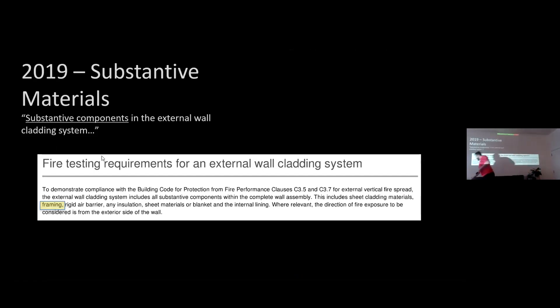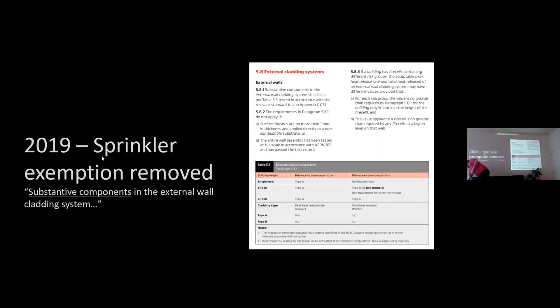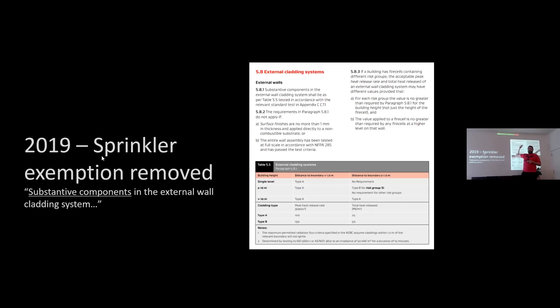2019 was actually a really important code clause for fires and combustible claddings — written really, really well. It had a couple of key things: it referred to 'substantive components,' which was a new concept — not just the cladding materials, not just the rigid air barriers. This was defined further on. It also said that now, even in sprinkler buildings, you can't just use whatever you want — there needs to be some level of surety on what they're going to do. No more sprinkler exemption; now looking at whole wall systems.